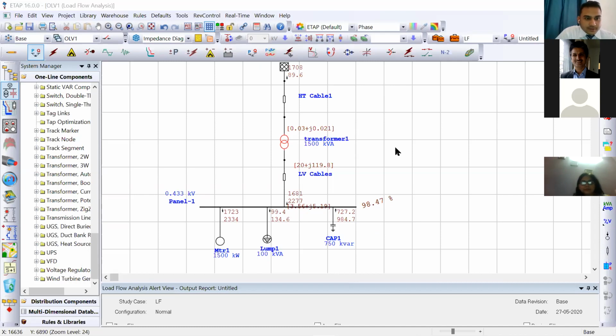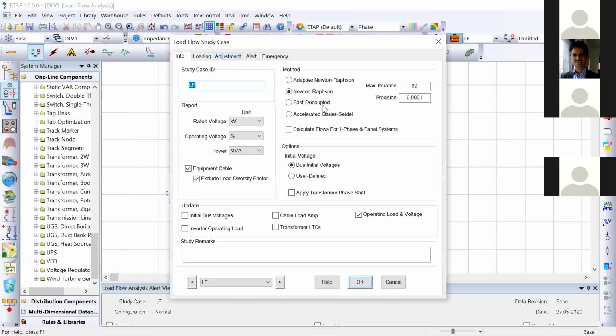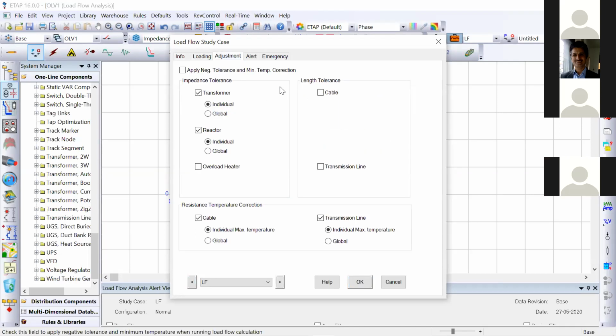Okay, so further, my partner Kapil Jani will take over. We will explain further on this. Yes, previous question somebody asked whether it can optimize, and as we explained, this is not a self-optimizing software, rather it's an analysis software. So you have to create different scenarios and optimize the system yourself. But yes, every point, every equipment, it will indicate if there is an error or not. Now these error modes also depend on the setting that is defined. You can change the different loading parameters. Practical conditions can be defined by the user.